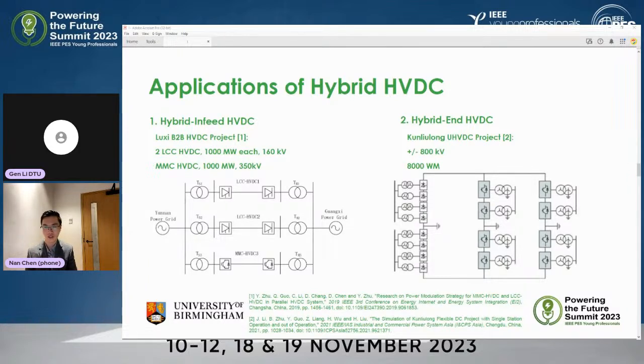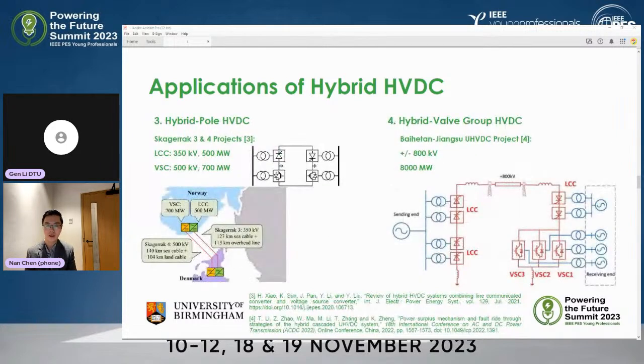The second one is hybrid end HVDC. The typical application is the Kunliulong ultra high voltage HVDC project with the voltage level of plus minus 800 kV and the total transfer capability of 8 gigawatt. Next page, please. The third one will be hybrid pole HVDC. It is applied in the Skagerrak 3 and 4 link project. It is a bipolar HVDC consisting of two technologies, one LCC link with the voltage level of 350 kV and 500 megawatt, and one VSC HVDC link with 500 kV rated voltage and 700 megawatt transferring capability.